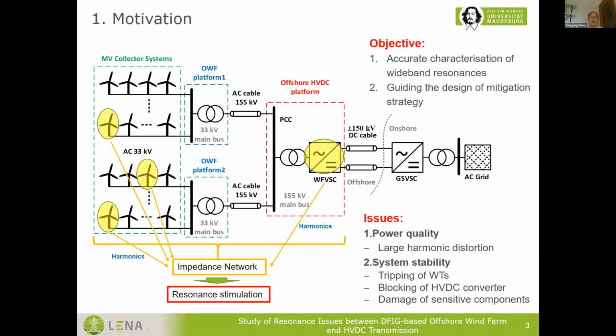Over the last decade, many offshore wind farms have been developed and integrated into grid through HVDC connections. Here is a typical configuration for such application. The interactions among wind turbines, HVDC converter, and the passive grid components can introduce wide frequency range of resonances, which may amplify the harmonic distortions or endanger system stability. Their consequences might be the tripping of wind turbines, blocking of HVDC converter, or the damage of sensitive components. The objective of this study is to accurately characterize the resonances, evaluate their risks, and provide guidelines for the design of mitigation strategies.